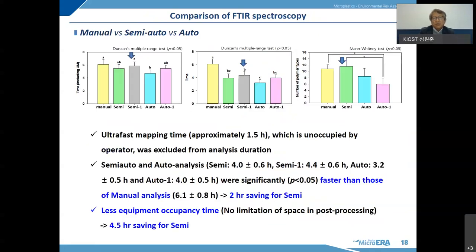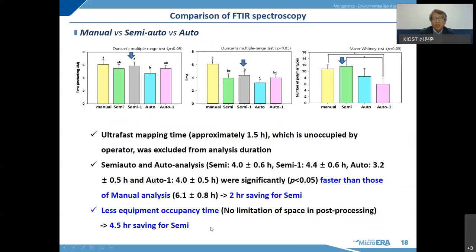This is the result when we compare the five FTIR spectroscopic methods. We carefully checked the time spent for analysis. When looking at the whole analytical time, the methods appear comparable. But ultra-fast mapping does not occupy operator time, so when we eliminate the ultra-fast mapping time, the semi-auto and auto methods are faster than manual analysis, saving approximately two hours. Another important point is that after ultra-fast mapping, the post-processing can be done on any computer installed with OMNIC software, meaning the instrument can be used for ultra-fast mapping of another sample. So when we count the equipment occupancy time, we can save 4.5 hours for semi-auto analysis compared to manual analysis — this is very important for managing laboratory equipment.